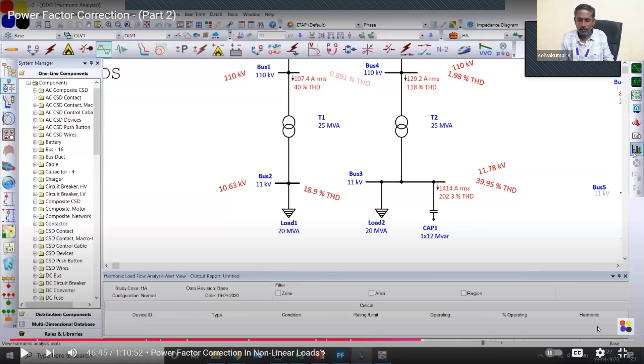Here it's an industrial power system, not a solar plant. You have a 20 MVA load with 18.9% voltage harmonic distortion and 40% current harmonic distortion. If the load has a lagging power factor and you add a capacitor bank to improve the power factor, instead of improving it, it destroys the power quality. You can see 18.9% THD becomes 40% THD, and the 40% current THD increases to 118%. You can possibly use that same capacitor as a filter by adding series reactors, etc. That has been explained in that video.